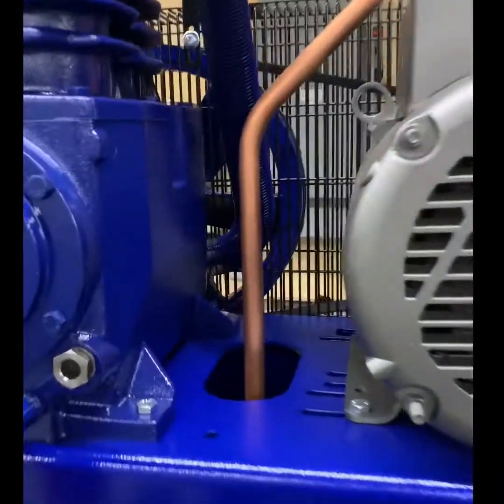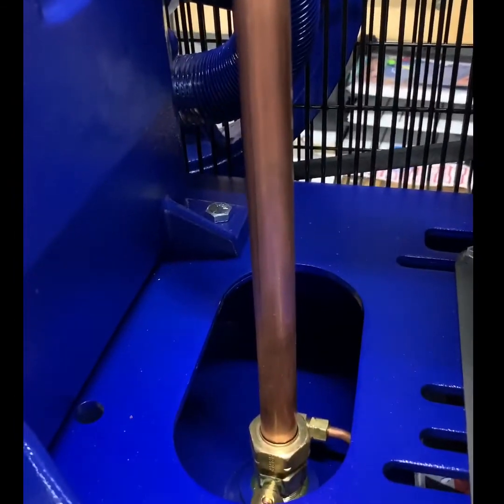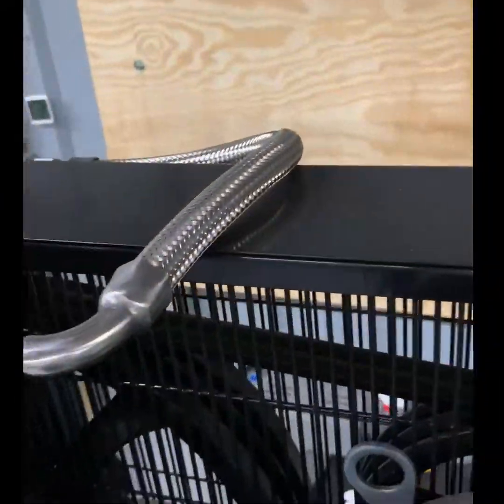The Quincy package is manufactured with a hard copper line installed with compression fittings to the check valve and the compressor head. Over time, these can break due to fatigue from vibrations. Our package is built with a stainless steel flexible line connected by JIC fittings.